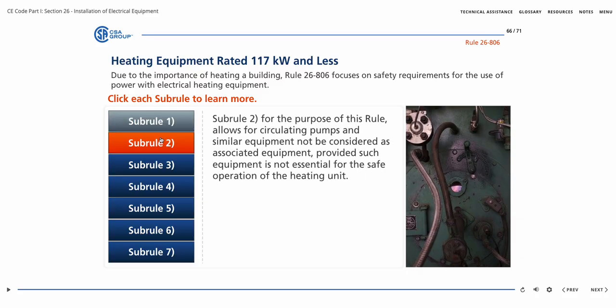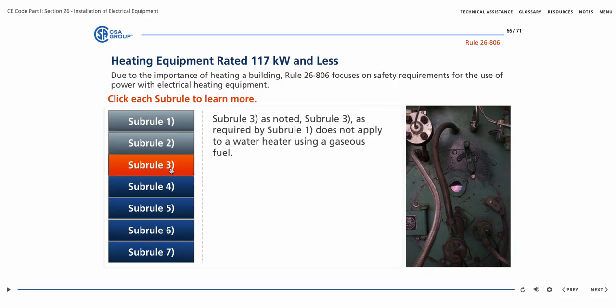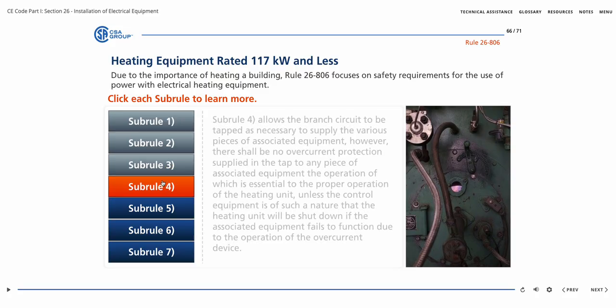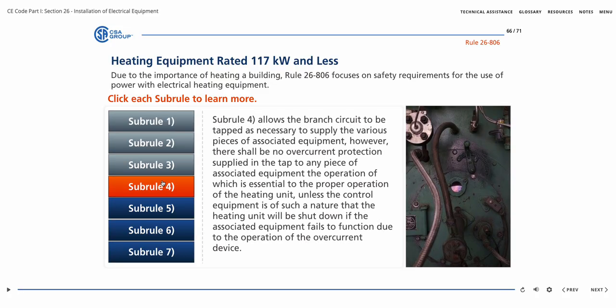For the purpose of this rule, Sub-Rule 2 allows for circulating pumps and similar equipment not to be considered as associated equipment, provided such equipment is not essential for the safe operation of the heating unit. As noted, Sub-Rule 3, as required by Sub-Rule 1, does not apply to a water heater using a gaseous fuel. Sub-Rule 4 allows the branch circuit to be tapped as necessary to supply the various pieces of associated equipment.